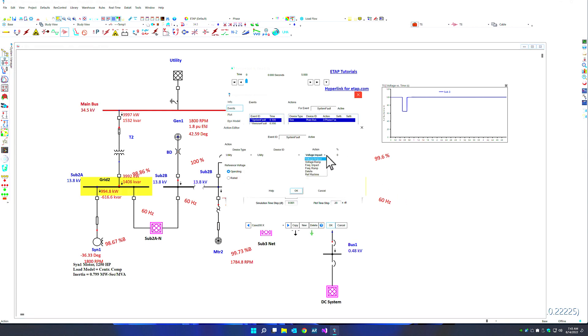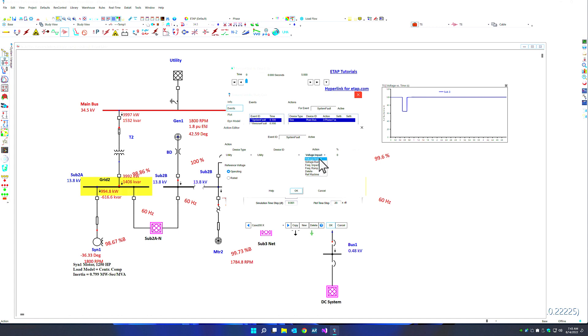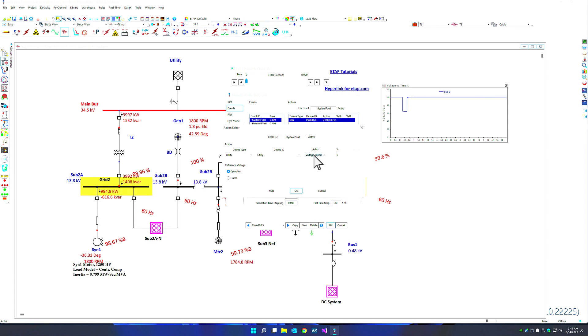In ETAP 22, you can also go to the utility and select between voltage impact ramp and frequency impact and ramp. And these options allow you to simulate the impact of high voltage ride-through or low voltage ride-through, including frequency ride-through capabilities by changing the behavior of the power grid and observing the response of the rest of the system with respect to the change in these actions.